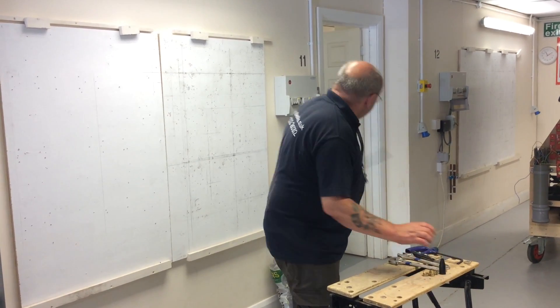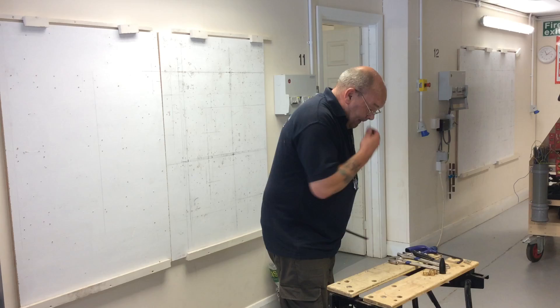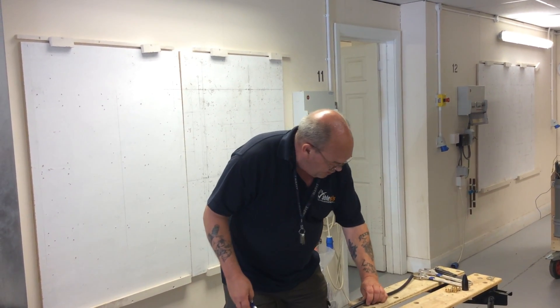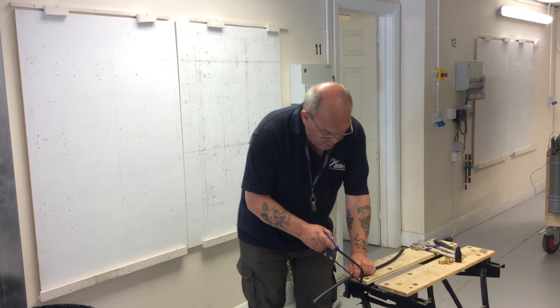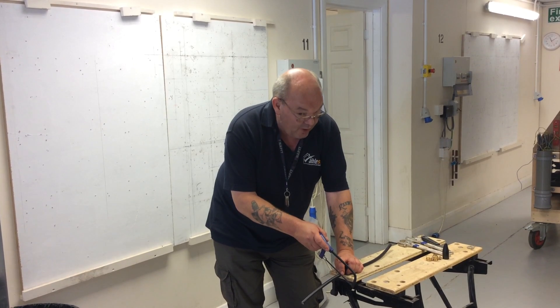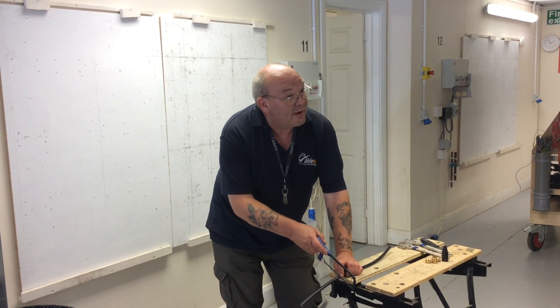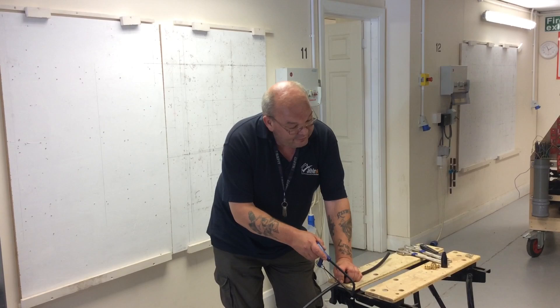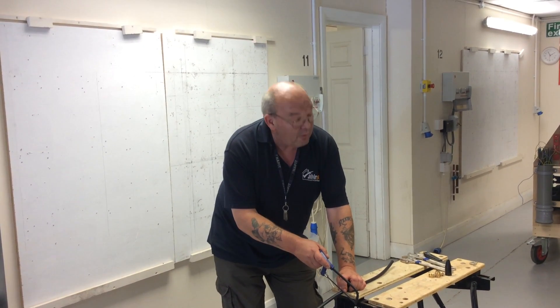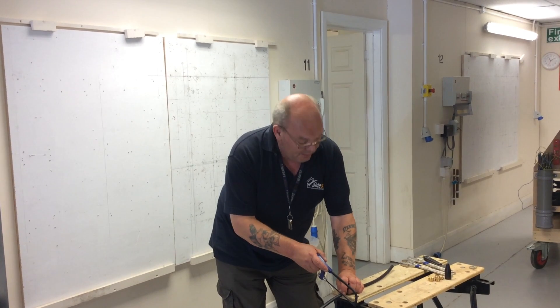What we have to do is obviously measure up. I'm only going to do a little bit, but what we have to do is go around the entire circumference, deep enough to penetrate the actual armour halfway or thereabouts. Get a practice piece first because the chances are you might mess up a couple — doesn't matter.